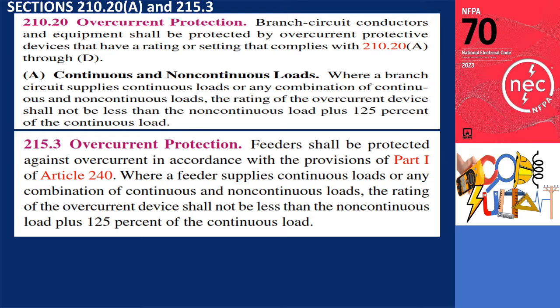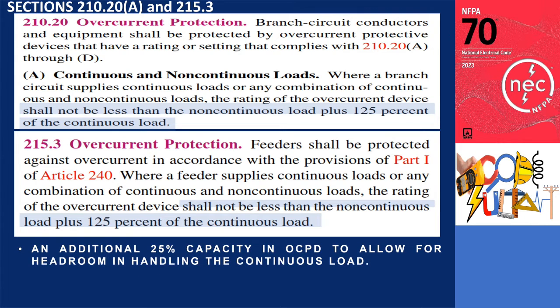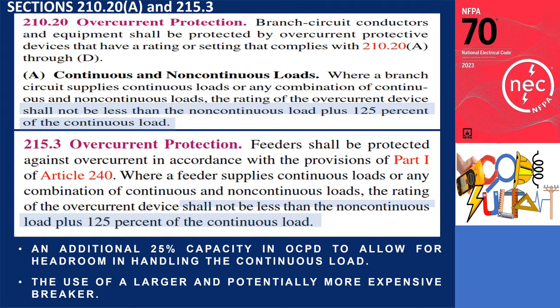Let's now explore the regulations regarding overcurrent protection. By following Sections 210.20A and 215.3, you can ensure that the overcurrent device can handle at least 125% of the continuous load plus the non-continuous load when branch circuits and feeders supply continuous loads or a mix of continuous and non-continuous loads. Essentially, the breaker or overcurrent device requires an additional 25% capacity for headroom in handling continuous loads, which necessitates the use of a larger and potentially more expensive breaker.